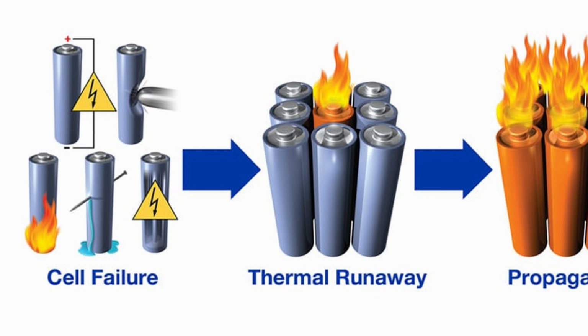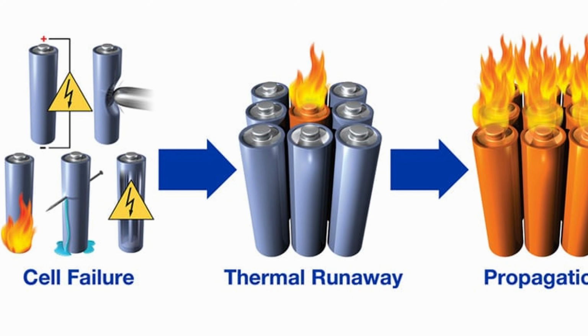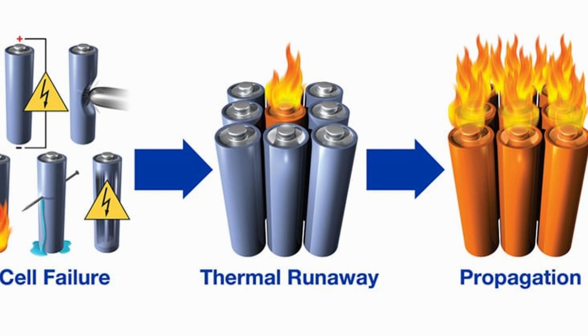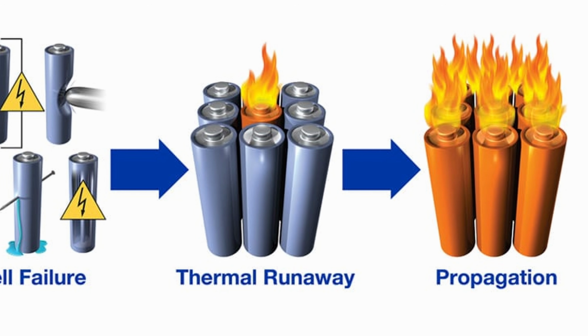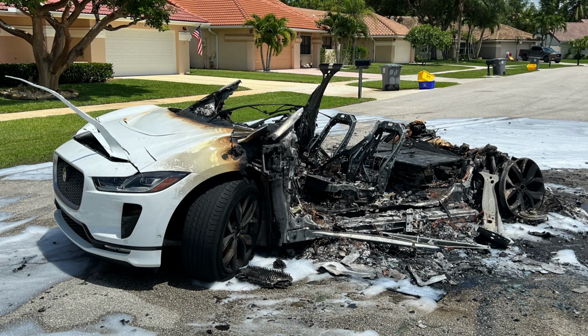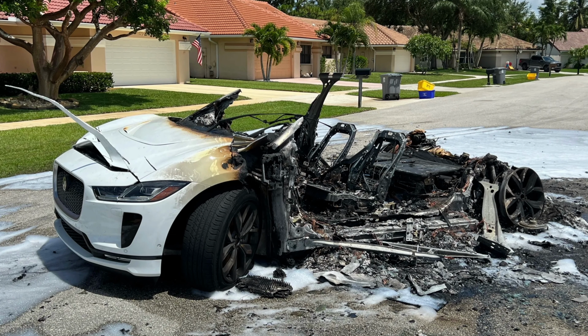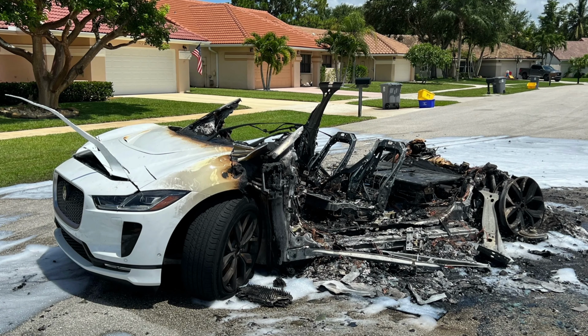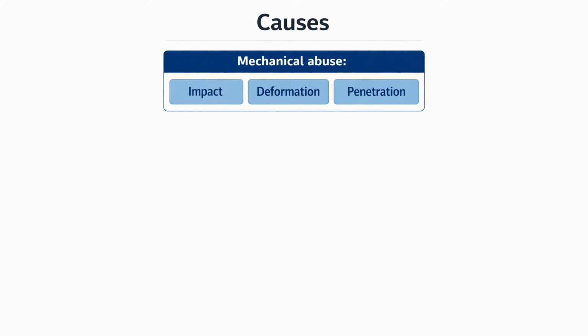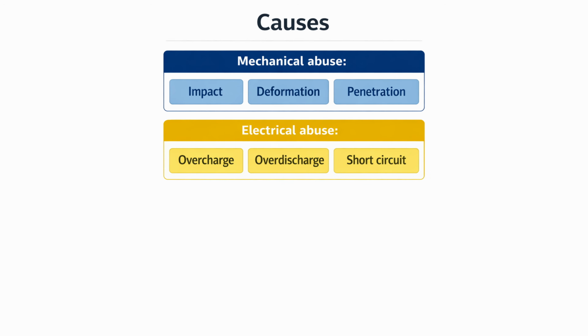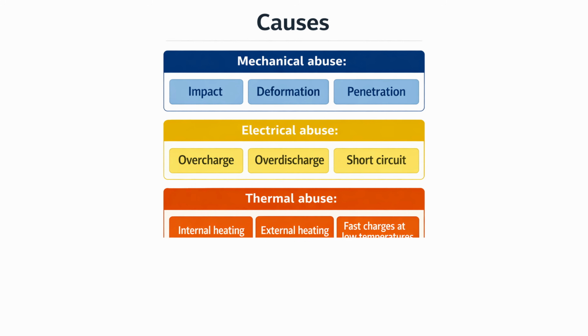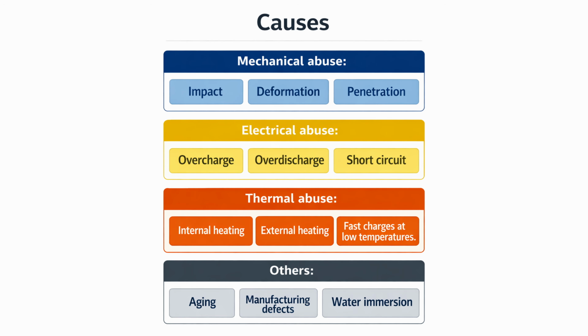Thermal runaway occurs when something inside a battery cell gets damaged or stressed enough that it starts heating itself faster than it can cool down. Once that happens, the temperature rises uncontrollably, the materials break down, oxygen is released inside the cell, and the cell basically becomes its own fuel source. This can be caused by 4 triggers. Mechanical damage, which includes crushing or puncture, electrical abuse, like overcharging, over-discharging or high current spikes, thermal abuse, like fire near the battery or a neighboring cell in runaway, and manufacturing defects, which can create an internal shortcut.